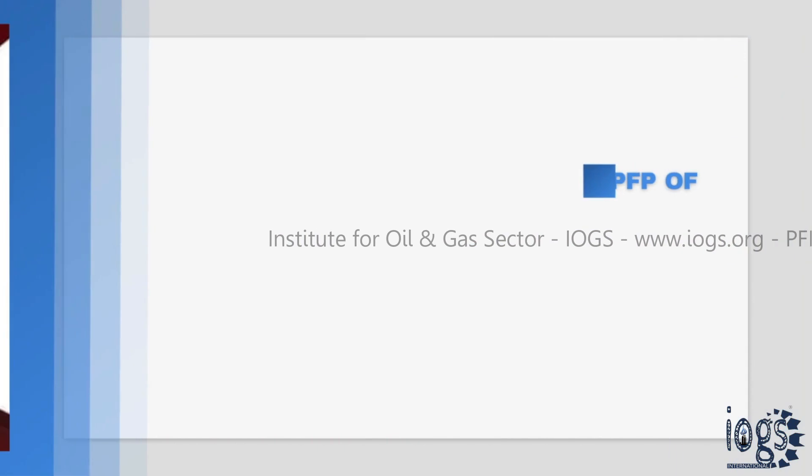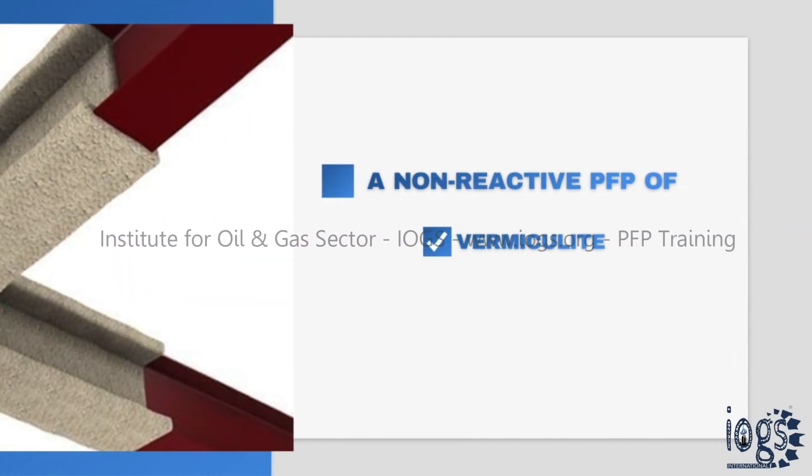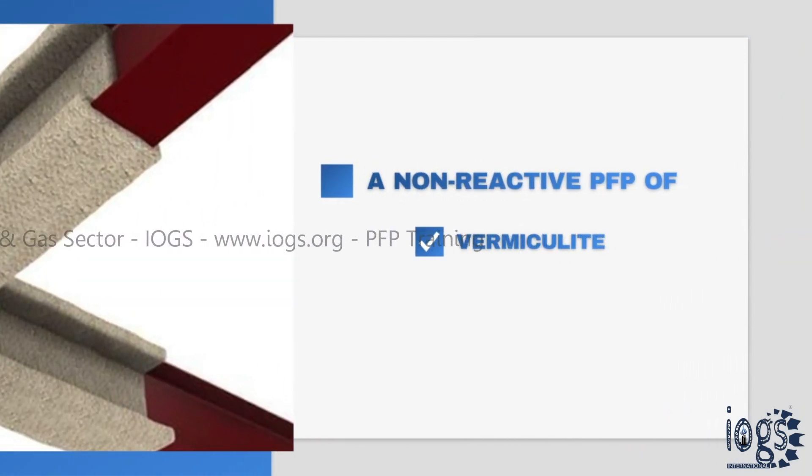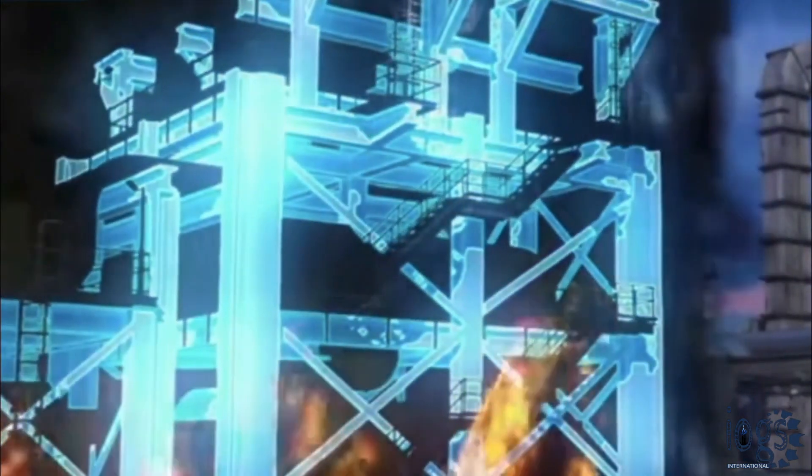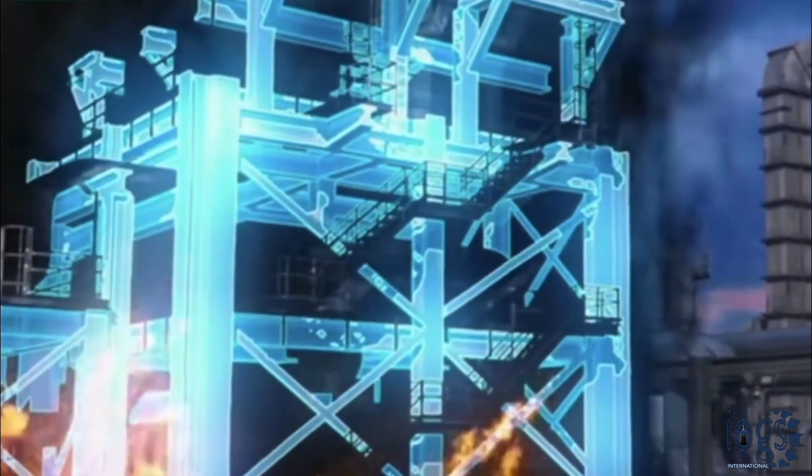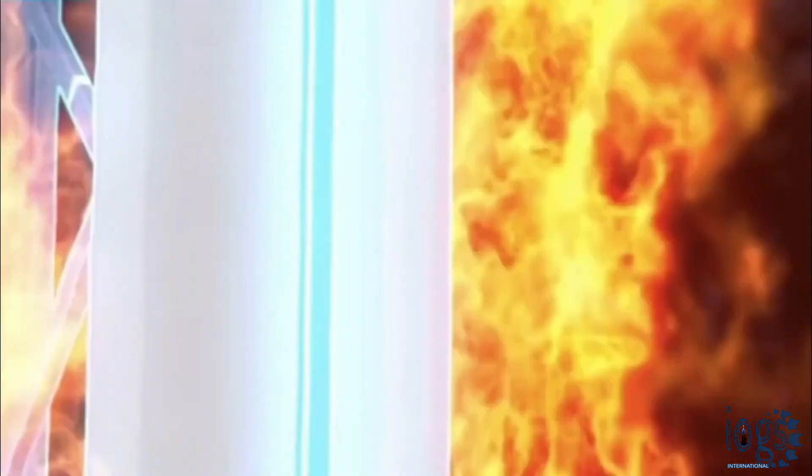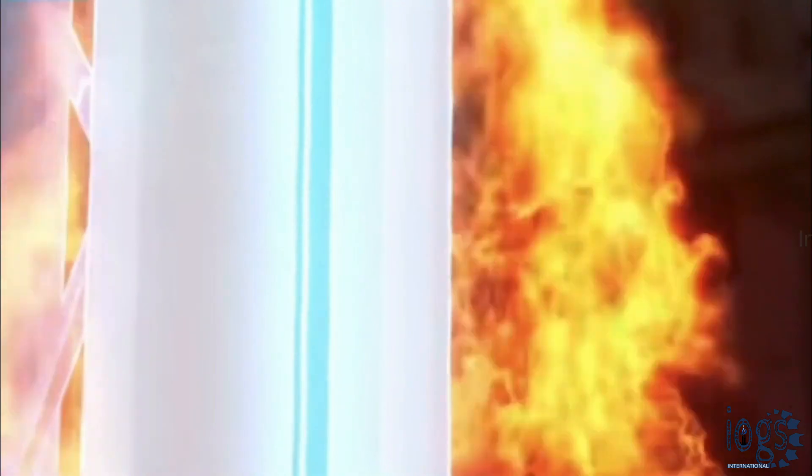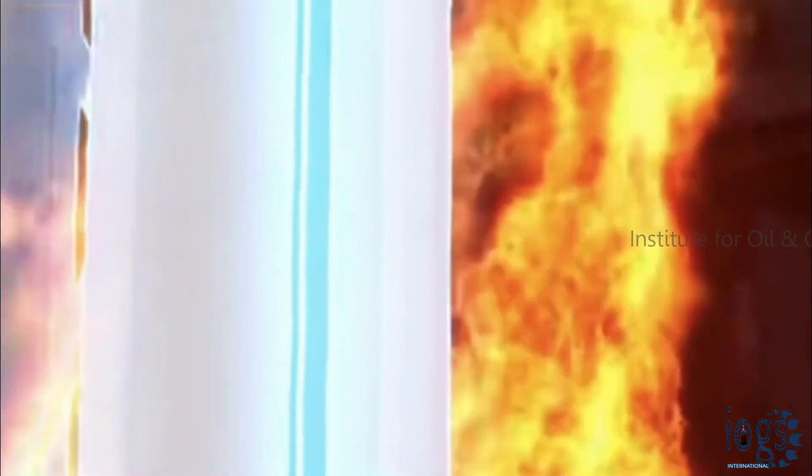In the case of cementitious fireproofing, the base material is vermiculite. Cementitious fireproofing has a cooling effect. It can keep moisture within itself, and later the moisture evaporates when the surrounding temperature is increased. After evaporating all the moisture as steam, the cementitious fireproofing uses its low thermal conductivity and high thermal resistance property to keep the fire away from the steel.